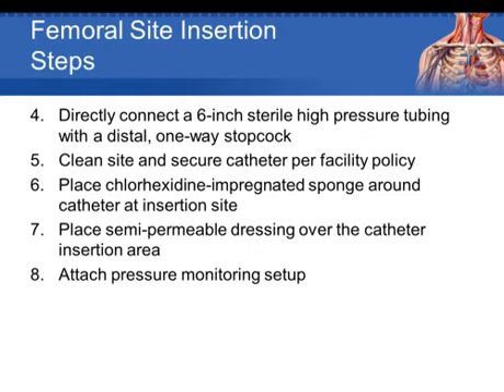The other thing it does with a one-way stopcock versus a three-way stopcock, it doesn't add any area for a clinician to draw blood out of it. Because if you draw blood out of a stopcock within a transducer setup, that stopcock has to be changed at a 24-hour interval for infection prevention reasons. So that is the reason that 6-inch piece of high-pressure tubing is in there and that distal stopcock.